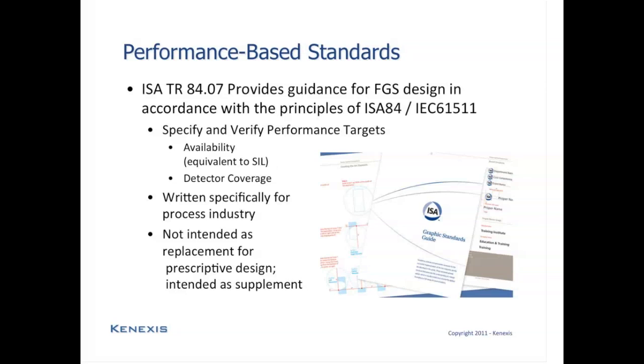84.00.07, and the purpose of this technical report was to provide guidance for fire and gas systems and how they can be designed in accordance with the principles of the ISA 84/IEC 61511 standard. And again, the IEC 61511 standard is the general international standard for safety instrumented systems, whereas the ISA 84 is the U.S. specific version of the IEC 61511 standard, which is essentially identical, other than a few additional sentences.